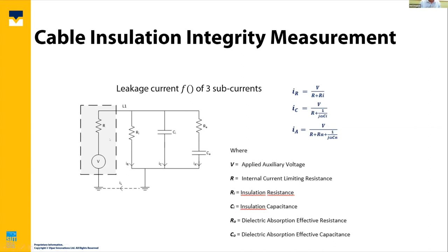So whilst it's a relatively simple voltage source, you can see that if you apply different AC signals, you can actually work out what the insulation resistance is, the insulation capacitance, and the dielectric absorption of the cable. So there's some basic electrical calculations, and then we can end up reporting those three elements.